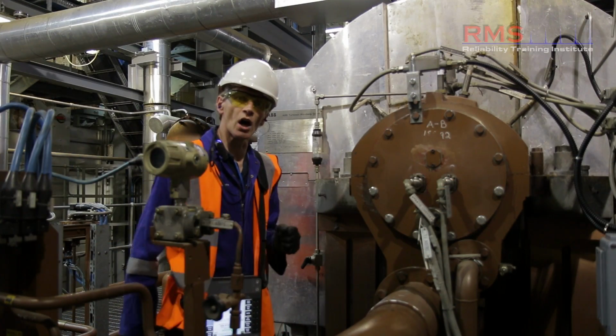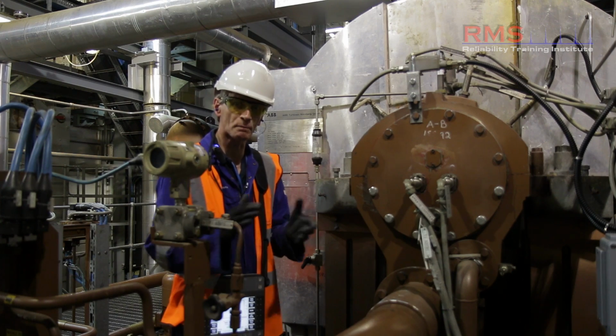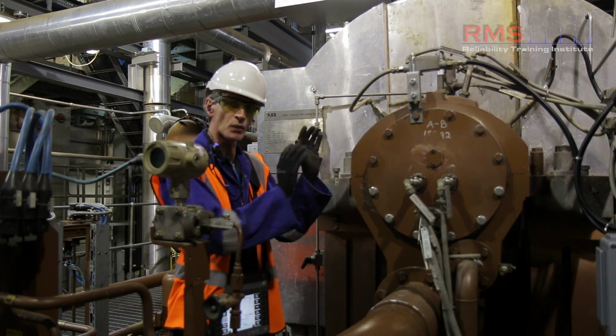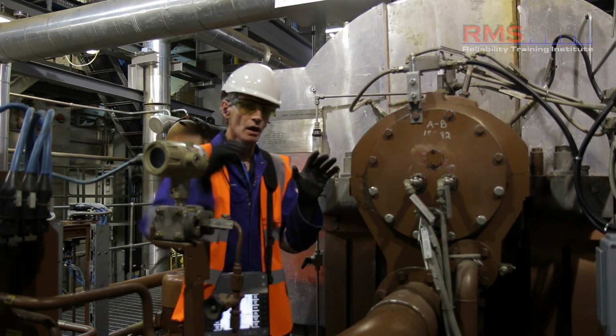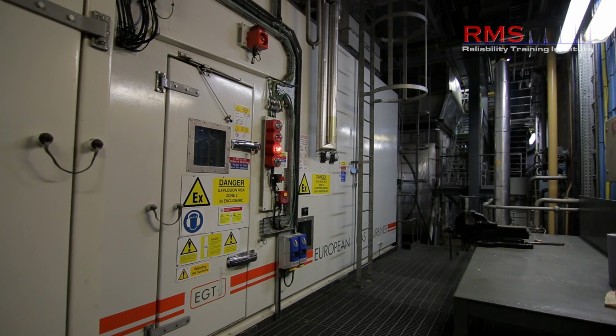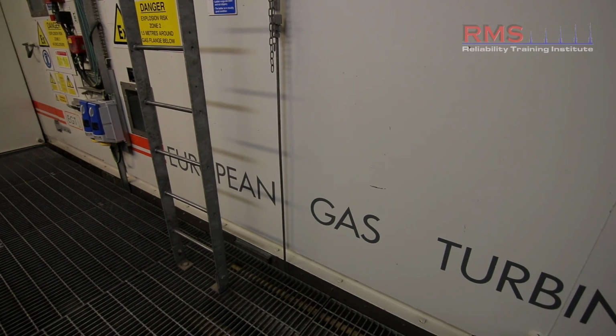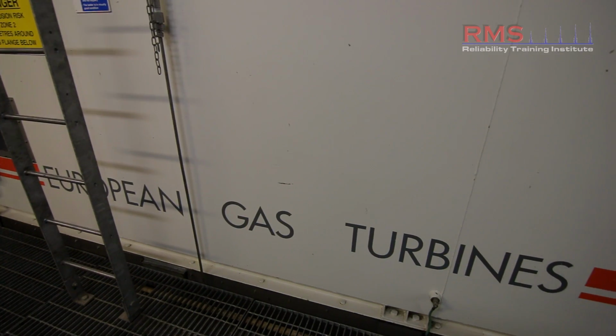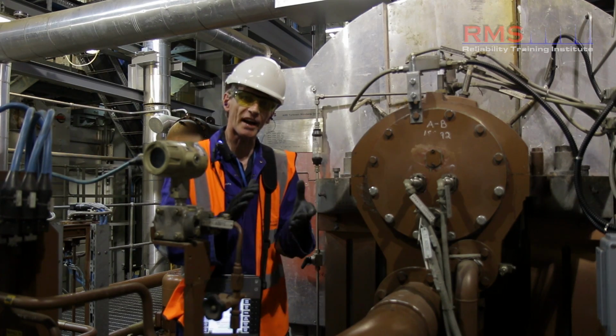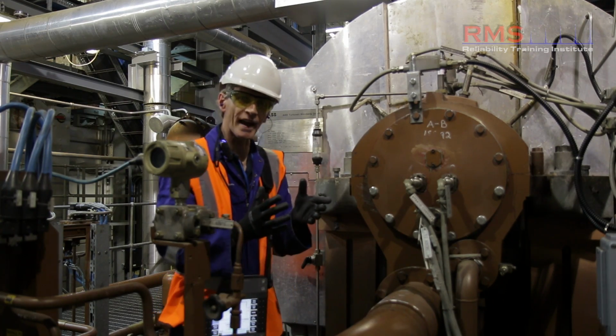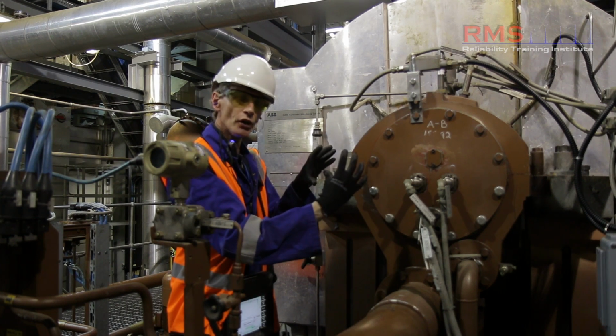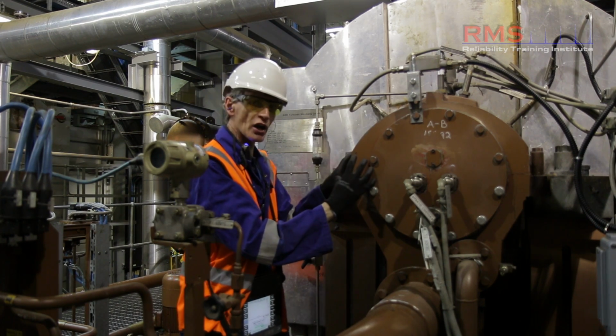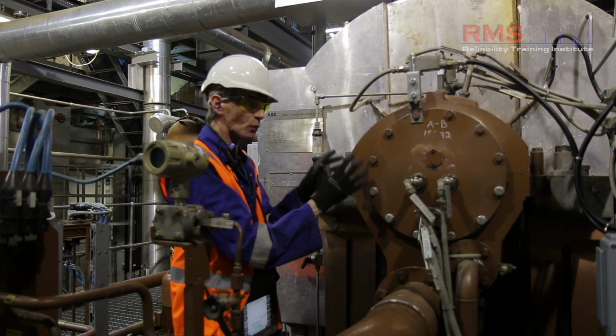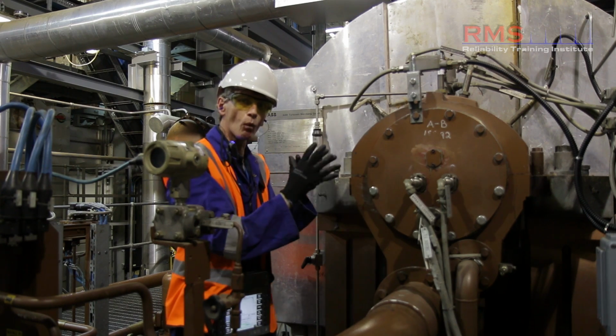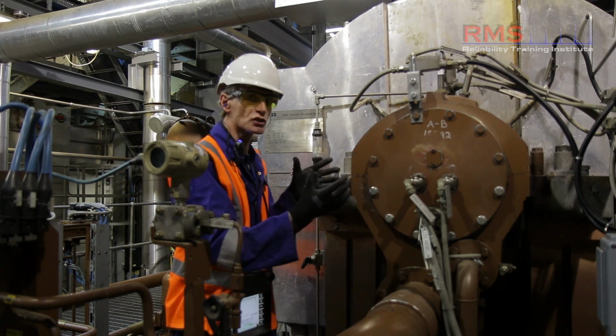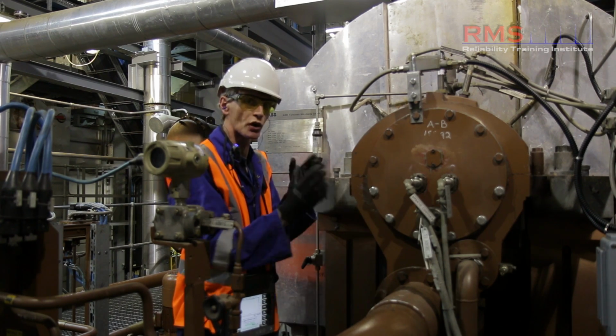Okay, so here we are alongside one of the prime movers at the CHP plant, the steam turbine, a 25 megawatt steam turbine. To my right, we have a 45 megawatt gas turbine. Both turbines have online vibration protection, which is monitoring the shaft movement of a shaft and a journal within a white metal lining.